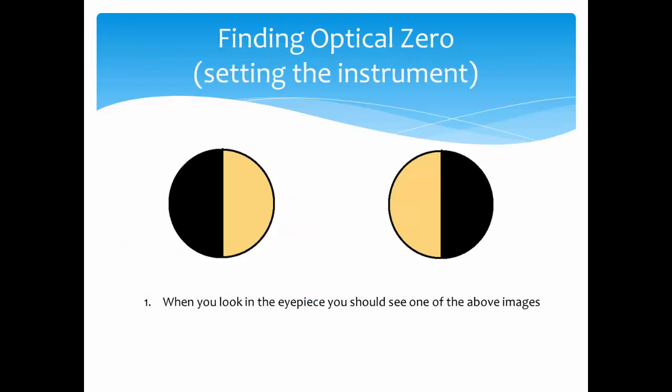In order to get a measurement, you must first find optical zero. To do this, look into the eyepiece once the tube is in the instrument. You should see one of the above images, either a black stripe in a light circle or a light line in a black circle.